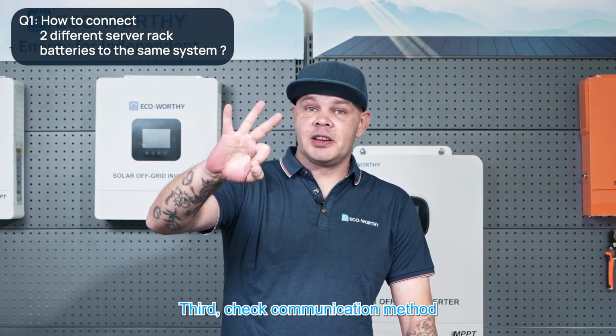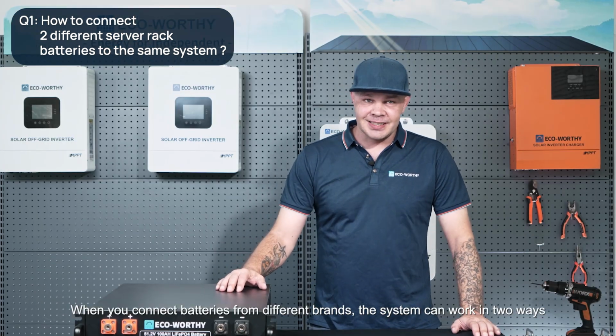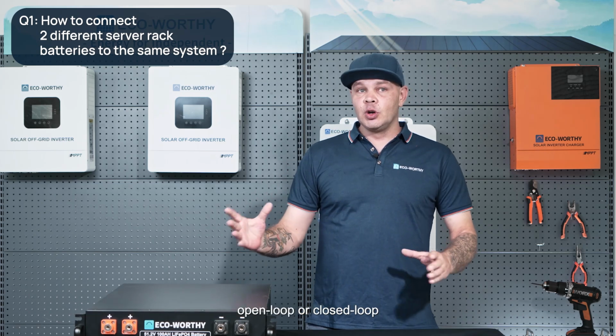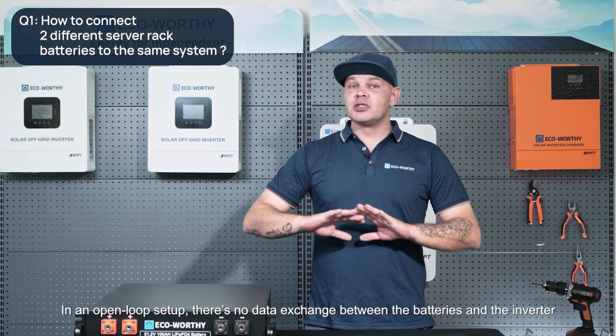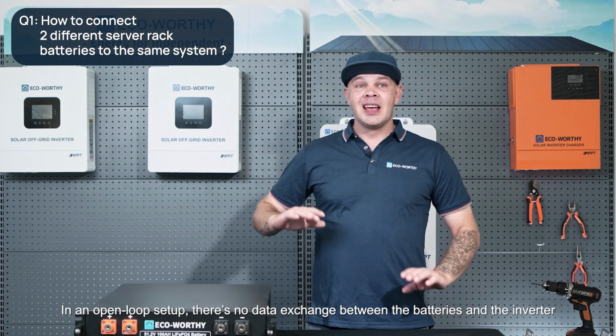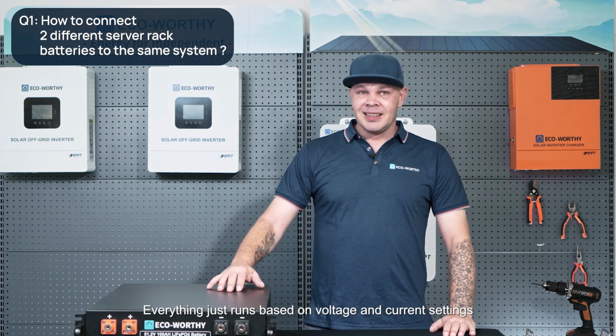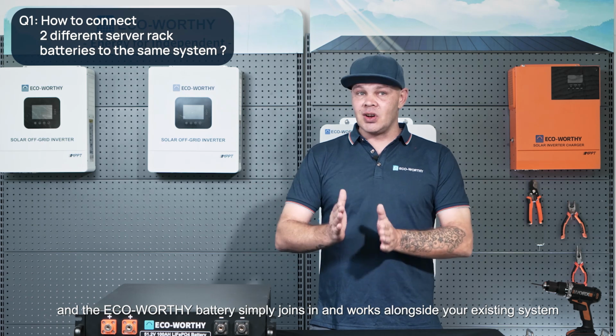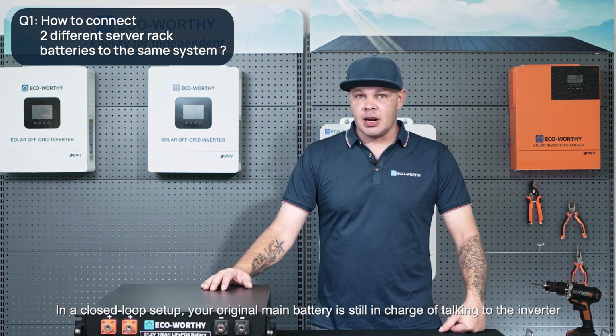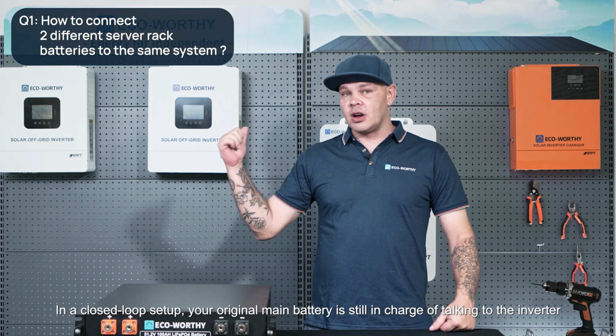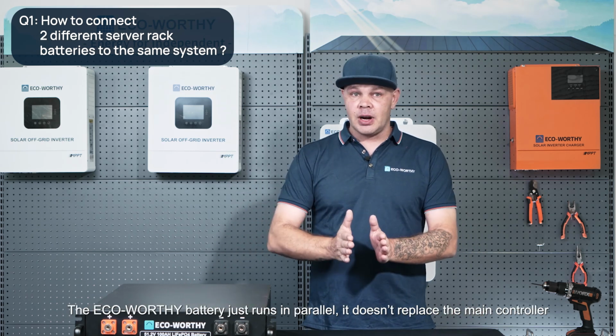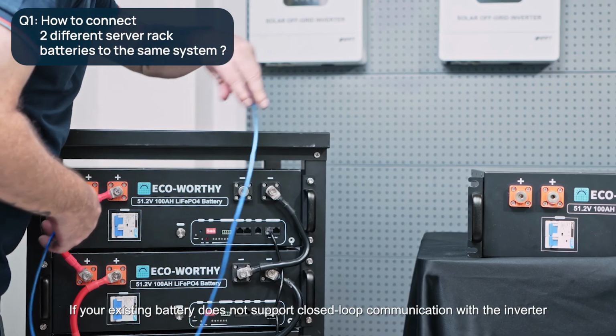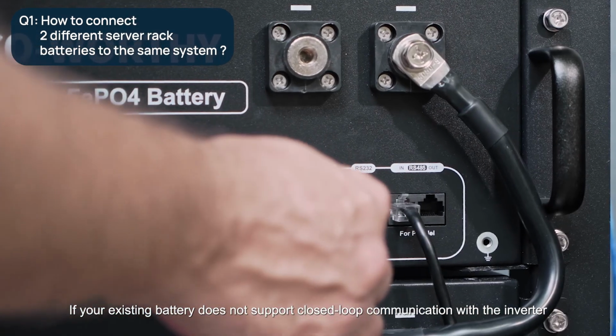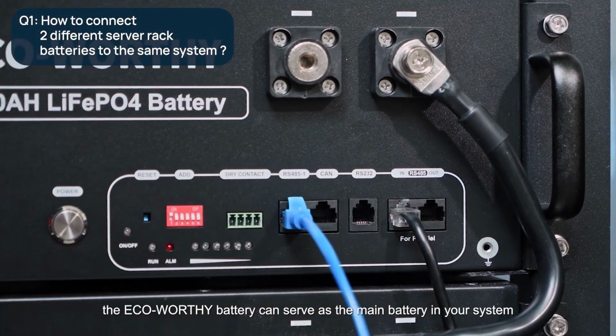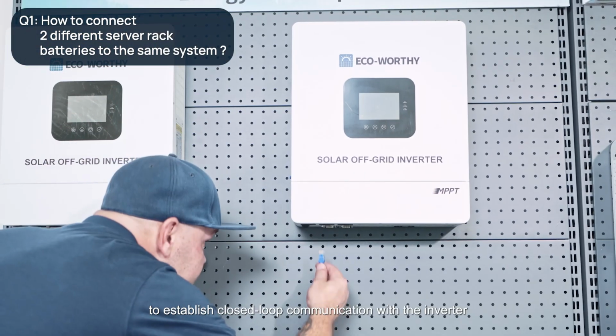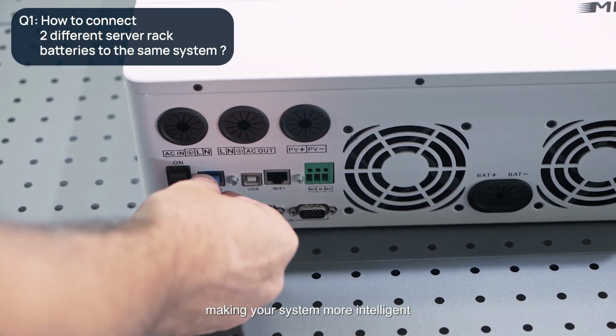Third, check the communication method. When you connect batteries from different brands, the system can work in two ways: open loop or closed loop. In an open loop setup, there's no data exchange between the batteries and the inverter. Everything just runs based on voltage and current settings. The eco-worthy battery simply joins in and works alongside your existing system. In a closed loop setup, your original main battery is still in charge of talking to the inverter. The eco-worthy battery just runs in parallel. It doesn't replace the main controller. If your existing battery does not support closed loop communication with the inverter, the eco-worthy battery can serve as the main battery in your system to establish closed loop communication with the inverter, making your system more intelligent.